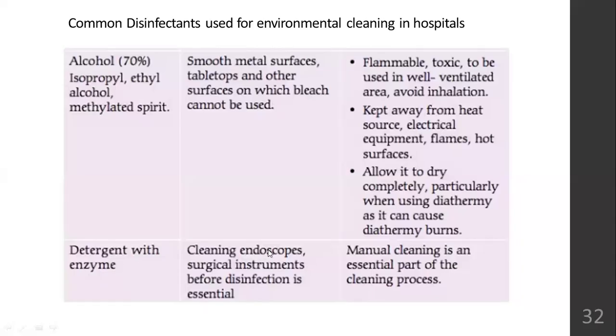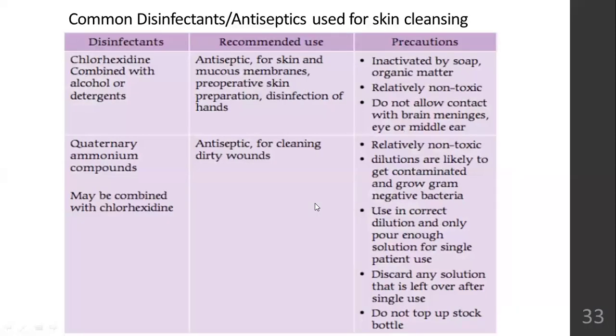Detergent with enzyme is used if you want to clean any fiber optic instruments: endoscope, laryngoscope, sigmoidoscope, colonoscope, laparoscope. For all these fiber optic instruments, detergent with enzyme is the ideal solution, but manual cleaning before that is very essential. Then chlorhexidine-based compounds are antiseptics that can be used on skin, for disinfection of hands, and any part of your body which is going to be operated, to clean that area before operation. Spirit can also be used, soap can also be used, but ideally, if chlorhexidine is there, go for it.